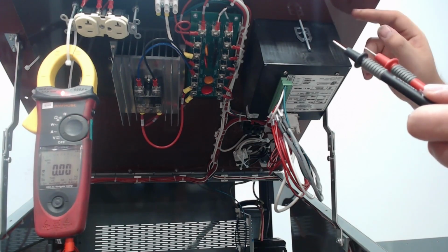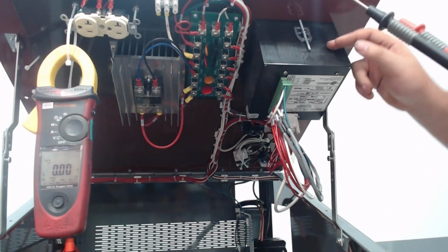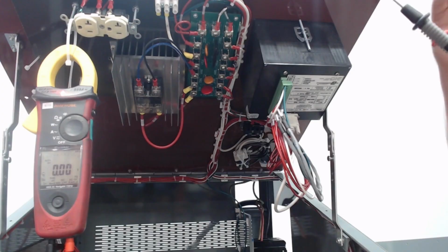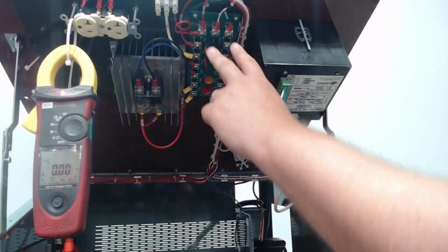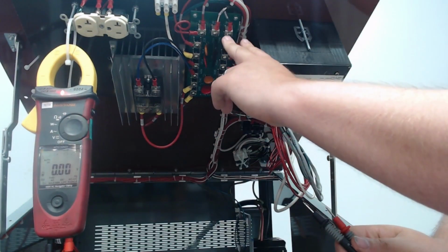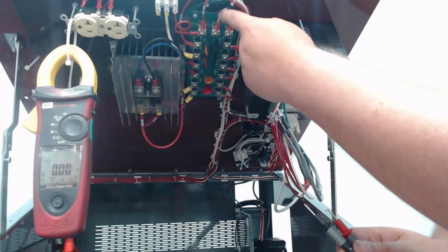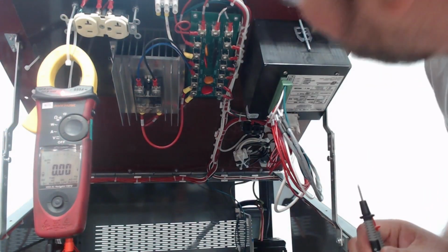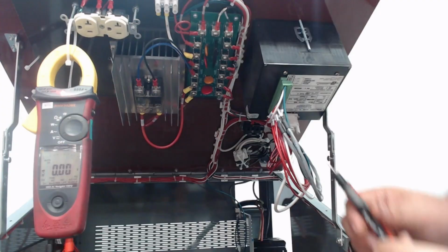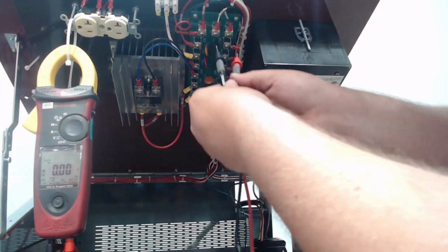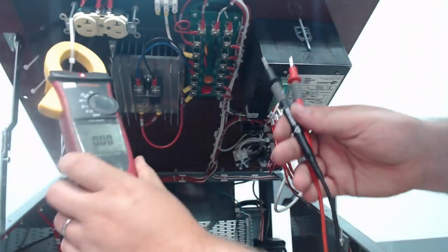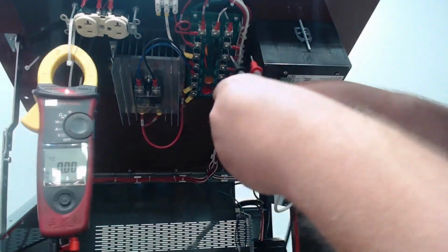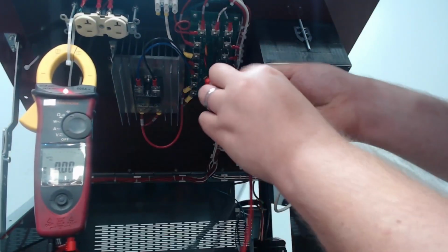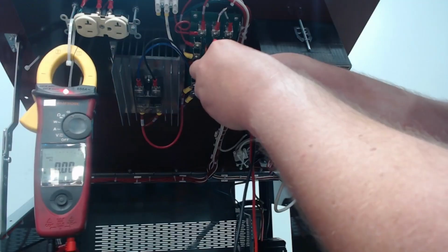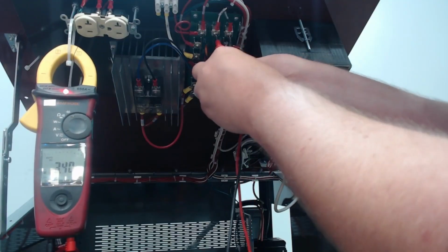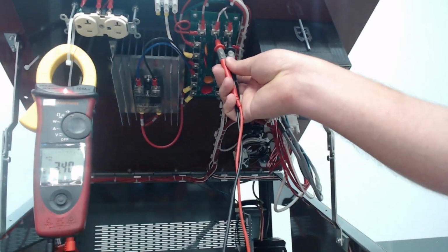So now, to check to make sure that contactor, for you, if your contactor didn't come on, the first thing you're going to do on a new unit is these two wires up here. There is a white and a black. It's 490 and 450. Those are the wire numbers. Now, polarity matters, and this is volts DC I'm checking. So the black is negative, and the white is positive.